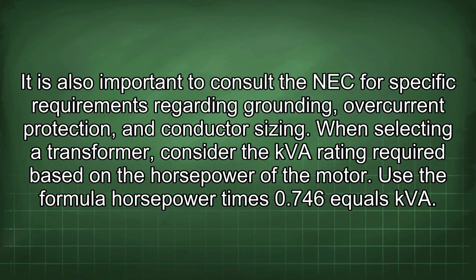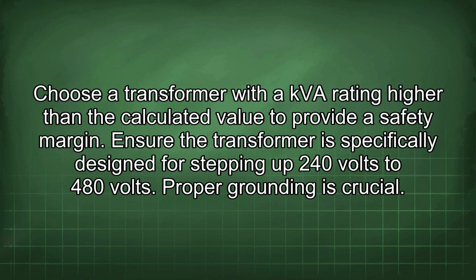Use the formula horsepower times 0.746 equals kVA. Choose a transformer with a kVA rating higher than the calculated value to provide a safety margin. Ensure the transformer is specifically designed for stepping up 240 volts to 480 volts.